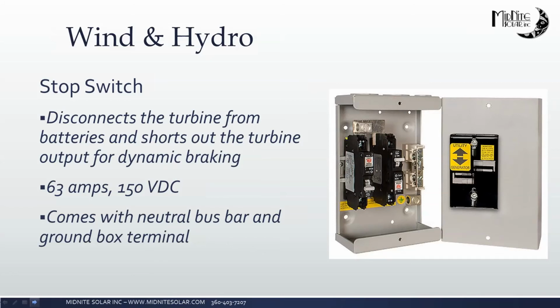Wind and hydro stop switches. Basically, just as they say, unfortunately the picture here shows a transfer switch sticker, but that's okay. It's the same box, it's the same slider switch, but essentially what we're doing is we're using one breaker as a run breaker, and we're using the other breaker as a shorting switch. So one of these breakers would get the turbine wired, the turbine would wire into the lug up here. One of them would get wired to ground, short the turbine out, the other one would get wired to your battery or your charge controller. So when you flip the bypass switch, you disconnect it from the load and you short the turbine out at the same time. That comes with 63 amp breakers in there. They're the biggest ones we make. You could retrofit 300 volt breakers if you're using a higher voltage turbine. But remember, the breaker in this is not an overcurrent protection as much as it is a switch.